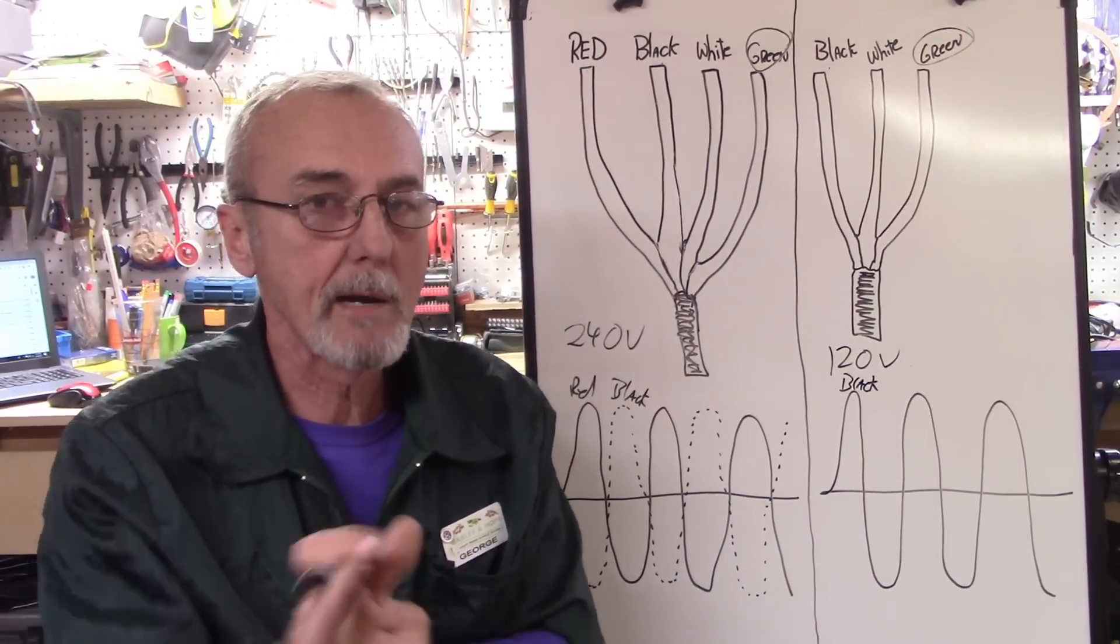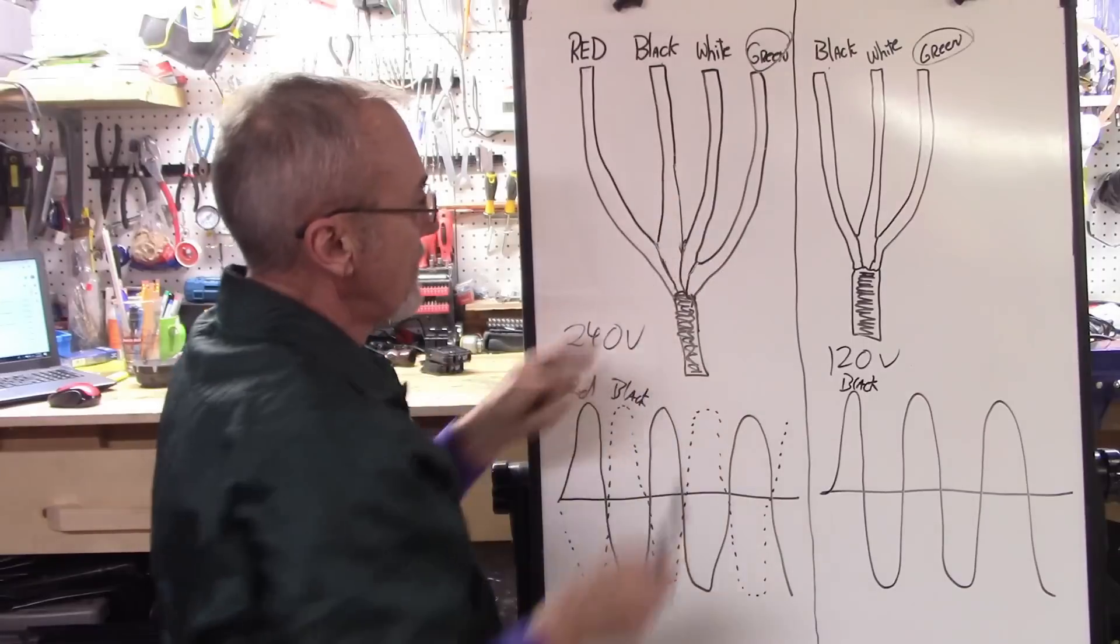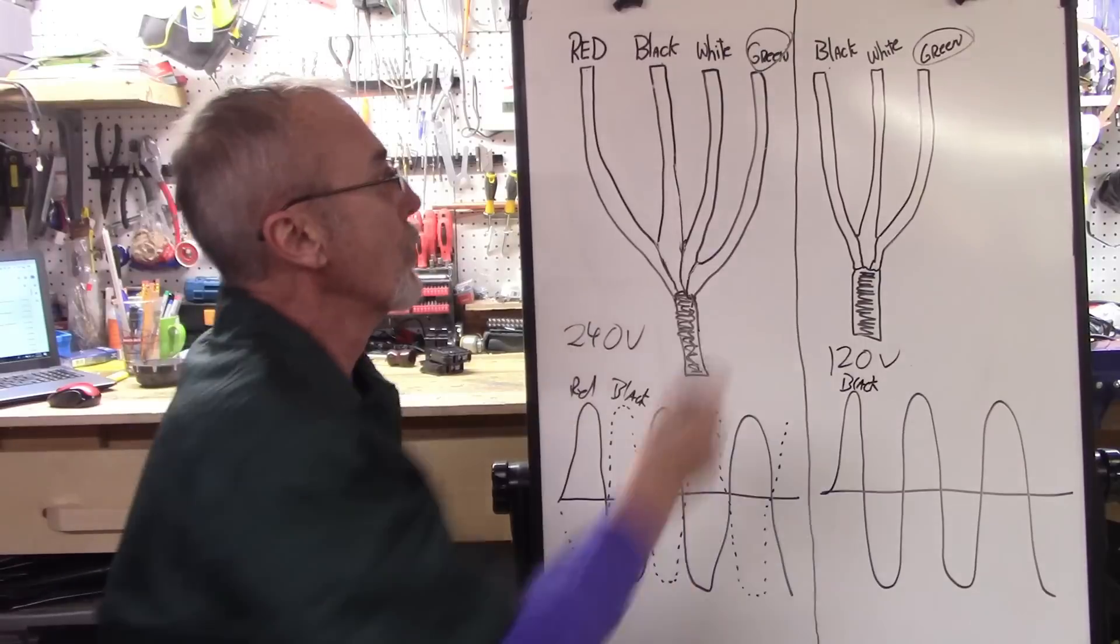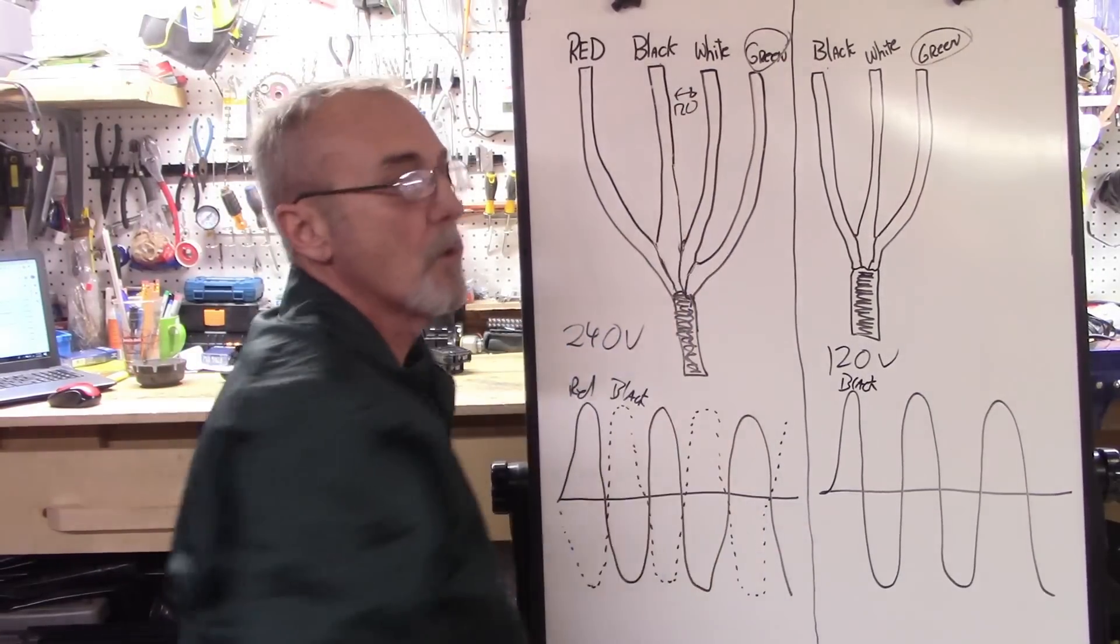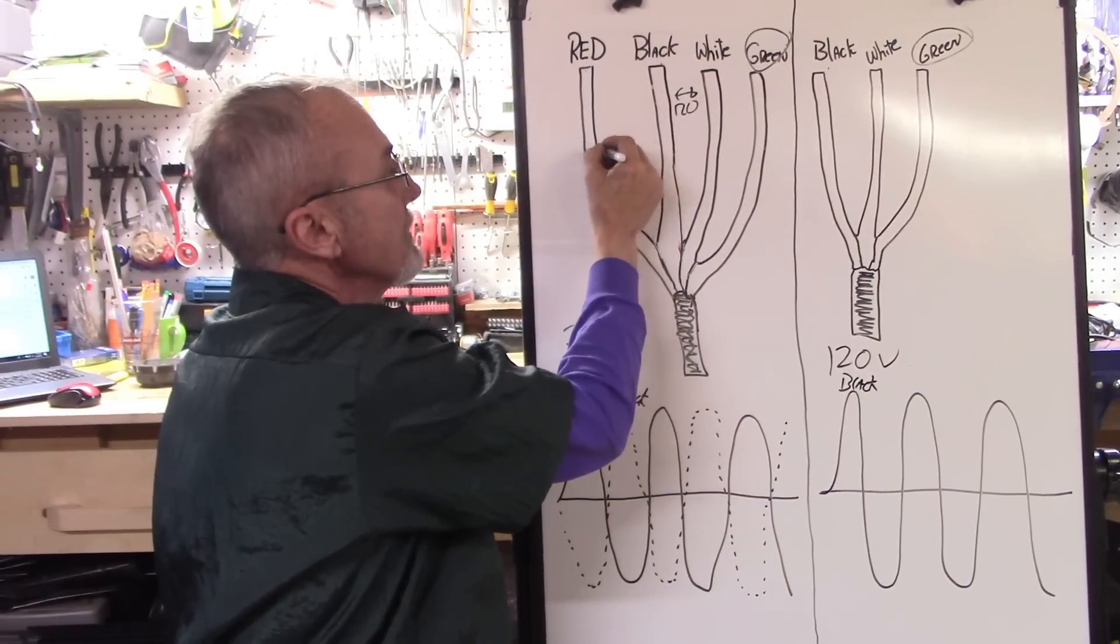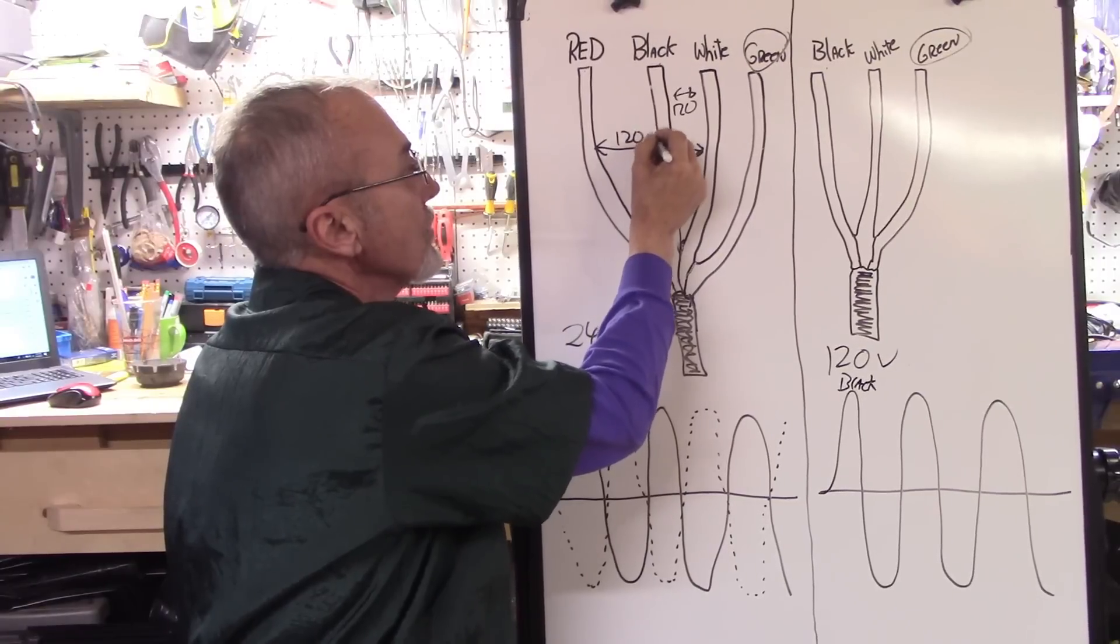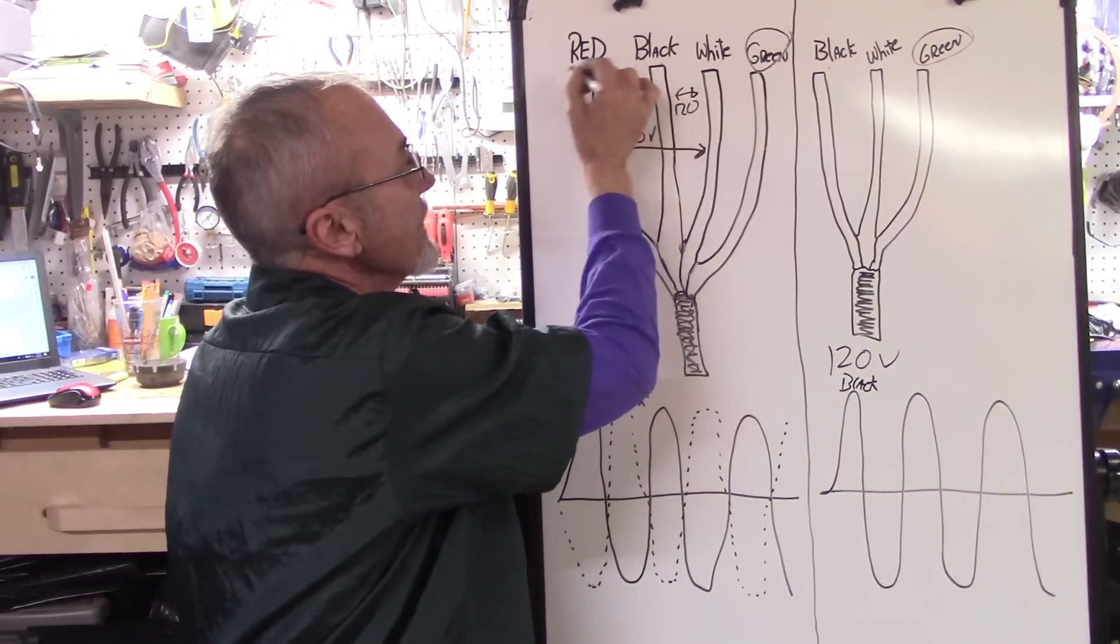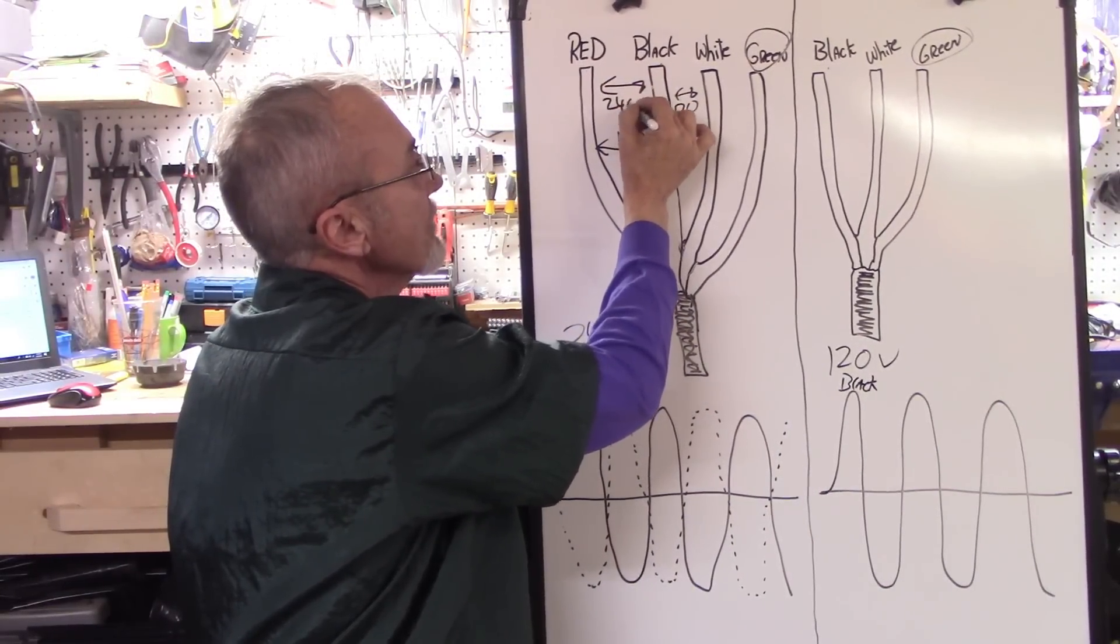A little bit more about ground later. But if we had a black and a white on this wire, because this is a 12-gauge 4-wire, if we used a black and a white, we would have between these two 120 volts. If we used just the red and the white, we would have 120 volts. If we use the black and the red together, is when we have 240 volts.